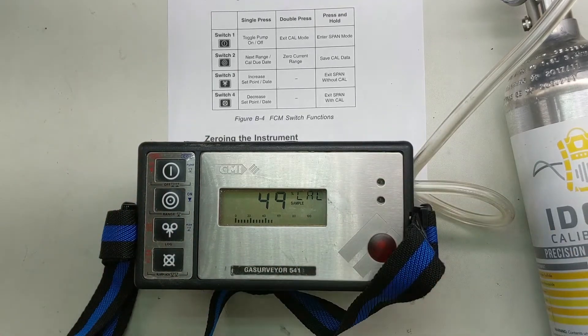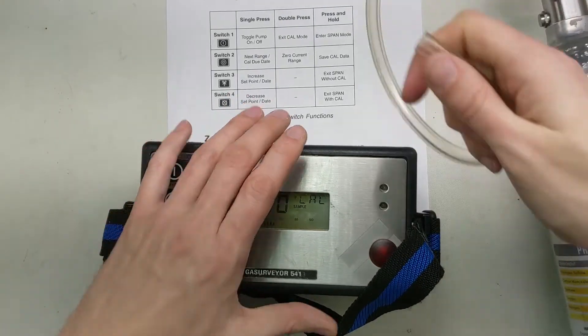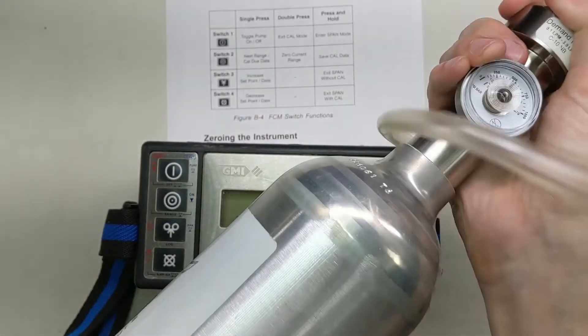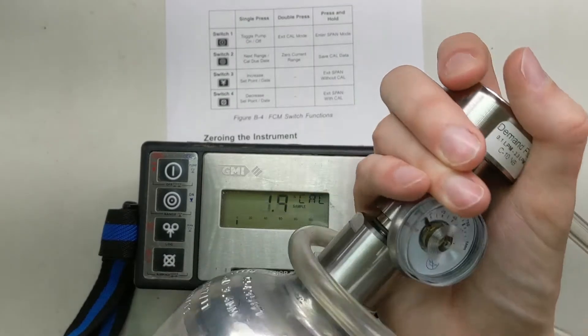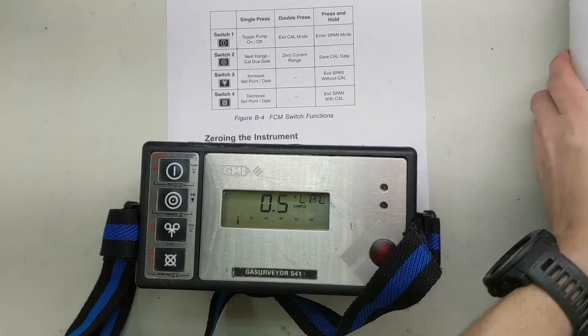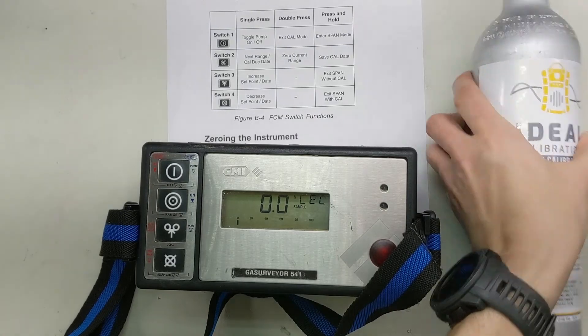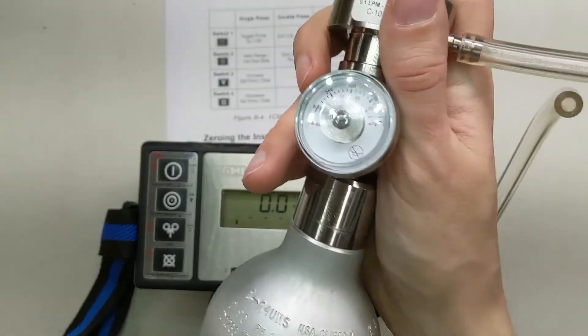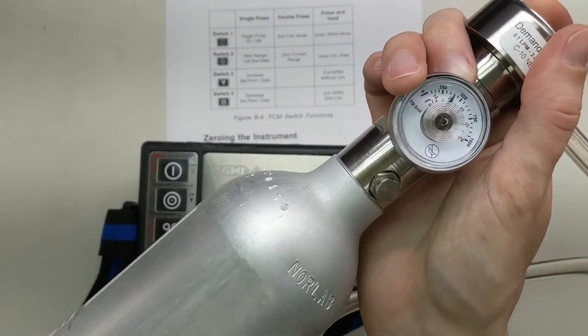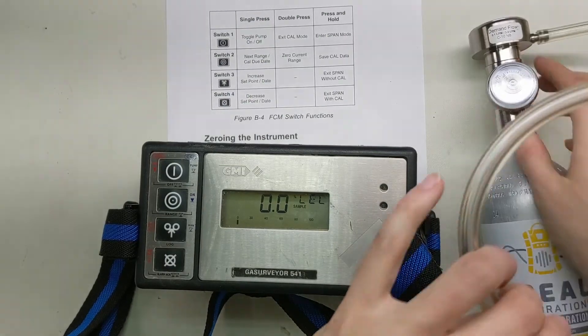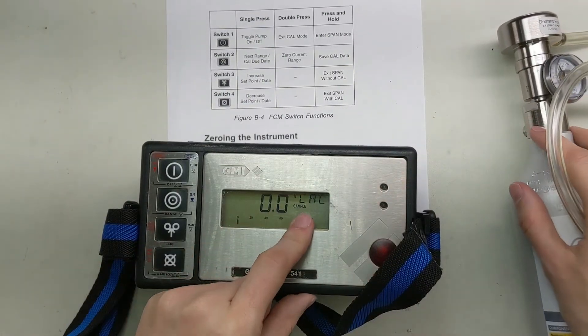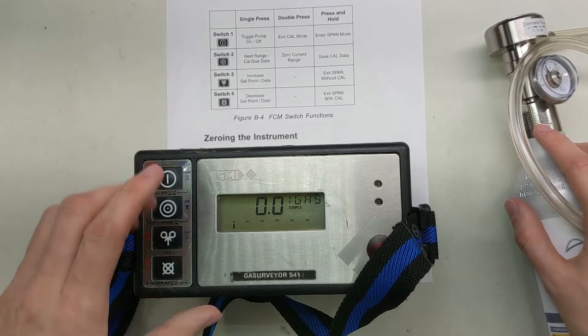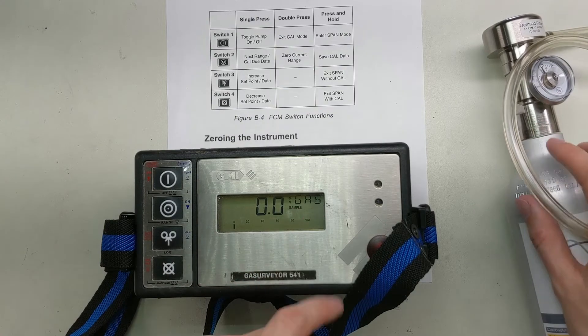Now we're going to move to the next cylinder. We're going to pop this off here. And now we're going to bring in the methane, UHP methane 99.97. Screw it in. Now it's in LEL mode right now. So what we want to do is we want to get one button more. Now it's got the V for volume, volume gas. Perfect. That's what we need.